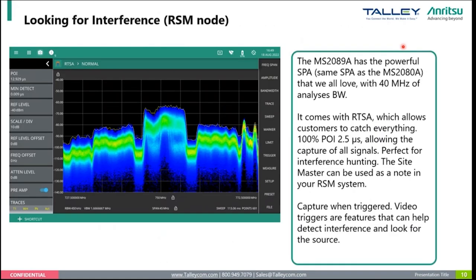The instrument has up to 40 megahertz of analysis bandwidth, which is very useful for a lot of applications out there. And we have 100% probability of intercept, as long as the signal is larger than 2.5 microseconds. In other words, we're able to capture everything that's coming in. There's no missing. With some instruments, when you don't have RTSA, you have capture bandwidth chunks at a time, and while it's sweeping, the signal might appear here. Well, when you park your center frequency and you have 40 megahertz of analysis bandwidth, we're able to capture everything here. And as you can see, as a result, you get this density graph. In other words, blue is less, and the darker it is, the more density of the graph. So you can actually see some stuff below the noise floor as well. This is great for interference hunting, for seeing intermittent signals. You're able to really see every signal that's out there.